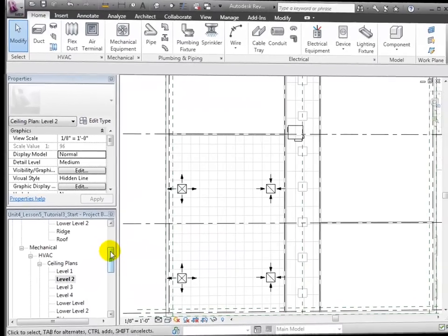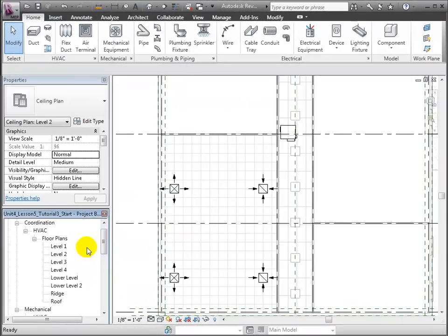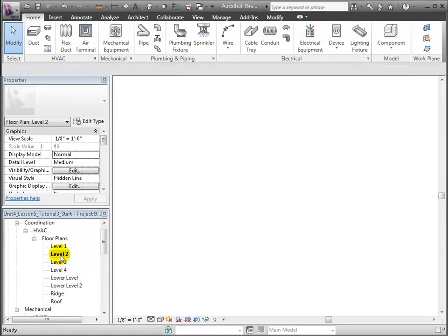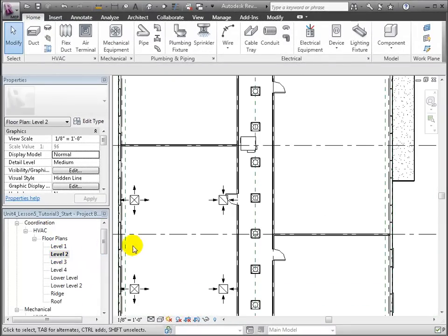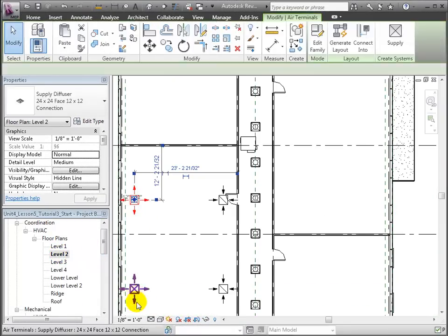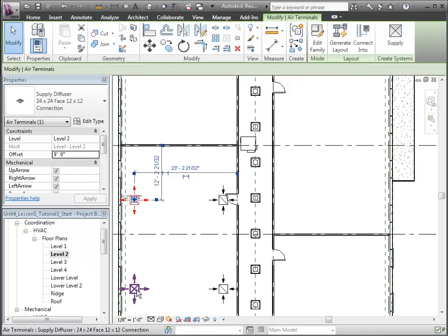Now let's connect these supply terminals to the air handling unit with ductwork. Since the closed plenum space itself serves as the channel to return back to the air handler, the return terminals won't need to be connected with ductwork. Select both of the supply terminals in the view.